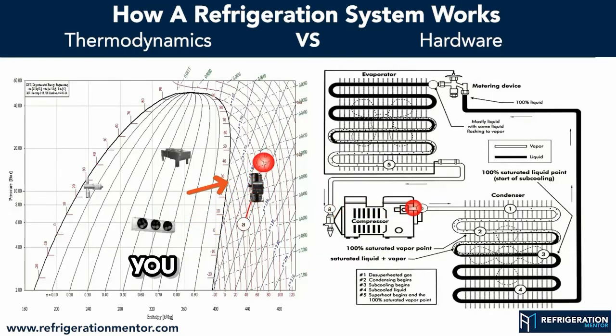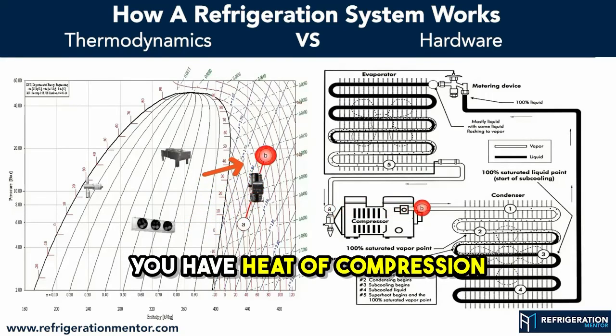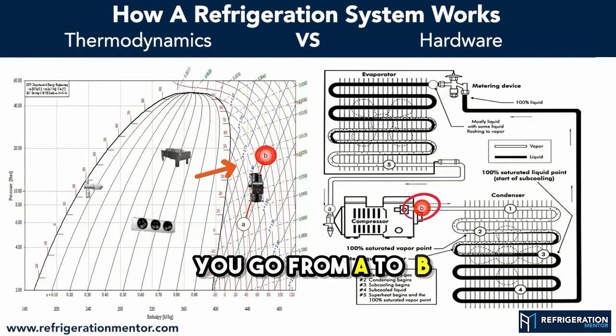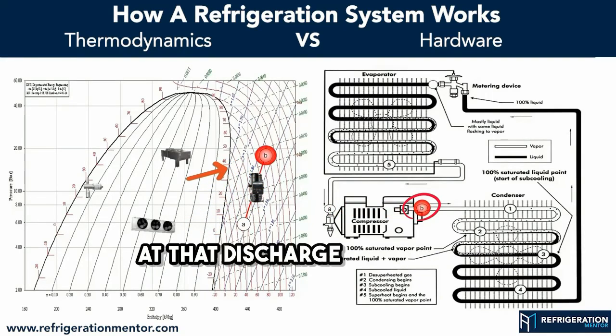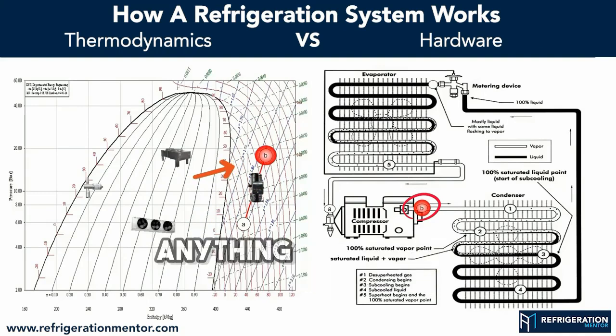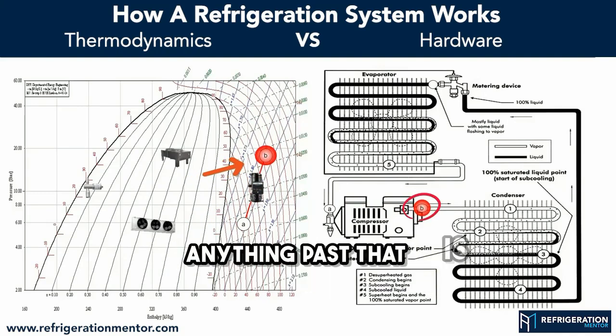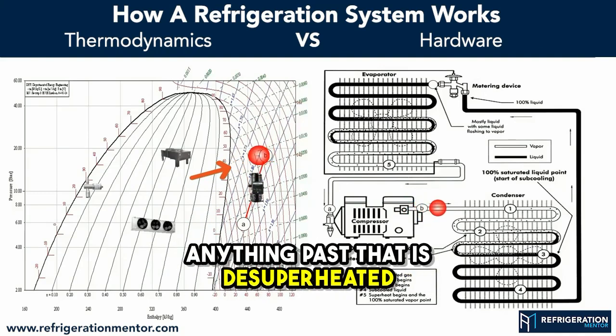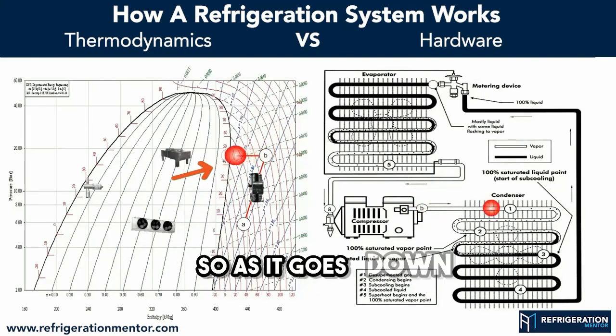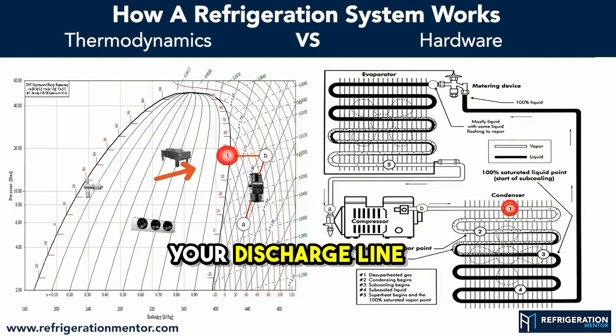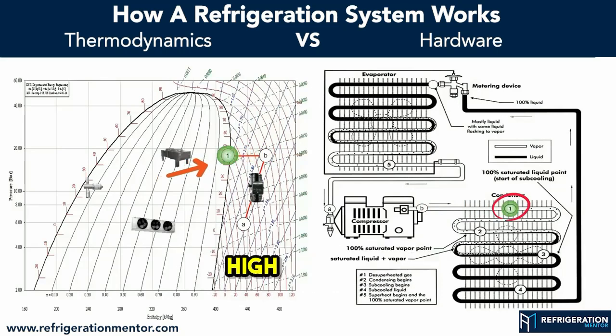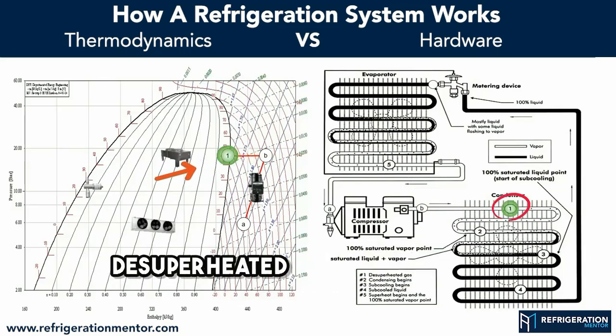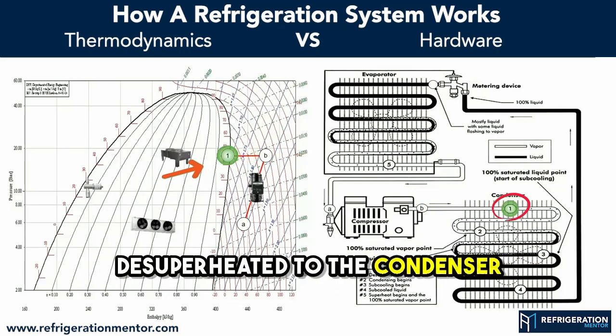As that compressor starts up, you have heat of compression — you go from A to B. At that discharge port, that's the hottest point. Anything past that is desuperheated. So as it goes down your discharge line, it's desuperheated — high pressure, high temperature gas — desuperheated to the condenser.